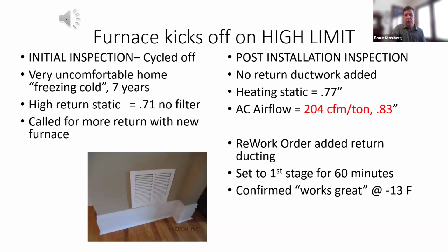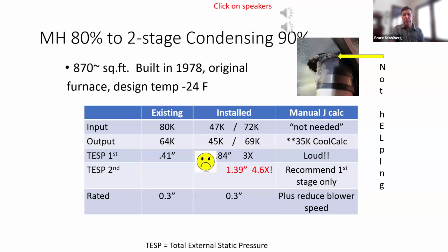Okay, so that home, on the start, definitely a problem, right? I don't know that any of us would expect that we should wear our winter coats when it gets cold out. We have heaters for that. This one here is a mobile home furnace. So kind of the same thing happens with mobile homes, although the ductwork is much smaller, so our issues become even greater. Static pressure is only rated at 0.3 instead of 0.5.